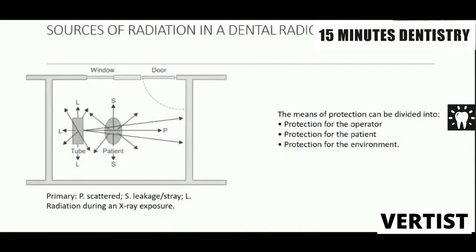Sources of radiation in the dental department: primary radiation comes directly out from the PID of the X-ray tube. Scattered radiation comes from the objects that are irradiated. Stray radiation, or leakage radiation, comes from the X-ray tube housing other than the PID. We need protection for the operator, protection for the patient, and protection for the environment.